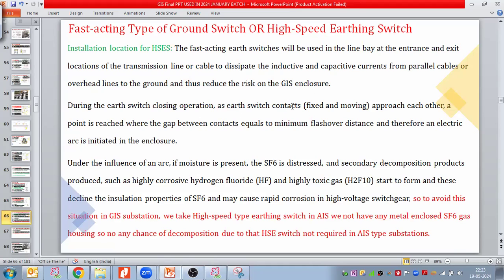During the earth switch closing operation, as the earthing switch fixed and moving contacts approach each other, a point is reached where the gap between the contacts equals the minimum flashover distance, and therefore an electric arc is initiated in the GIS enclosure. Under the influence of an arc, if moisture is present, the SF6 gas is decomposed and secondary decomposition products such as highly corrosive hydrogen fluoride and highly toxic gases start to form. These weaken the insulating property of the gas and may cause rapid corrosion in high voltage switchgear as well. So to avoid these situations in GIS substations, we take the high speed type earthing switch. In AIS, we do not have any metal enclosed gas housing, so there is no chance of decomposition. Due to that, a high speed earthing switch is not required in AIS type substations.